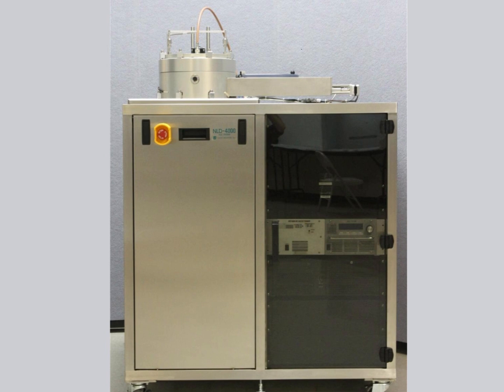It is CE and SEMI standards compliant and capable of processing up to 8-inch wafers. The system is controlled with LabVIEW software and features 3-level password-controlled user authorization using a touchscreen monitor. The system is fully automated, safety-interlocked, recipe-driven, with status indicators and graphic and alphanumeric displays.